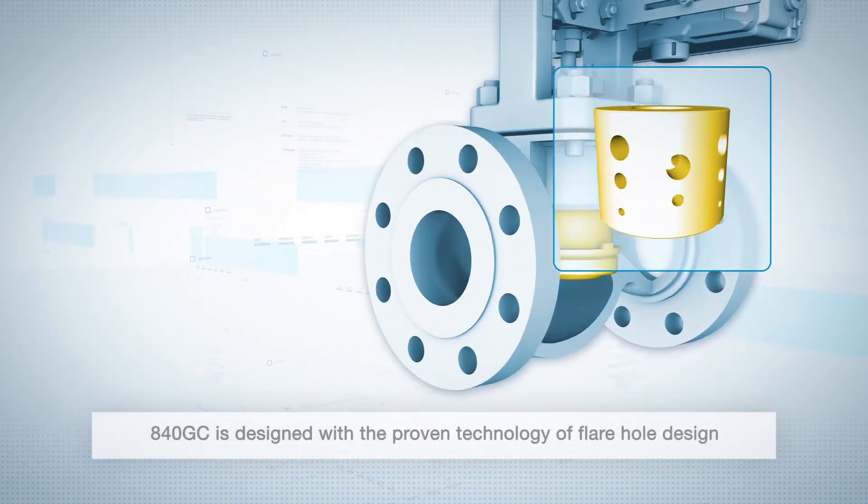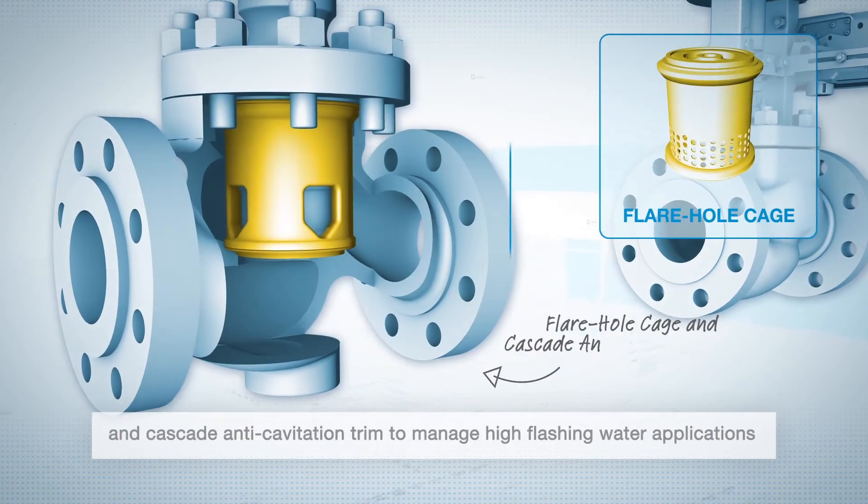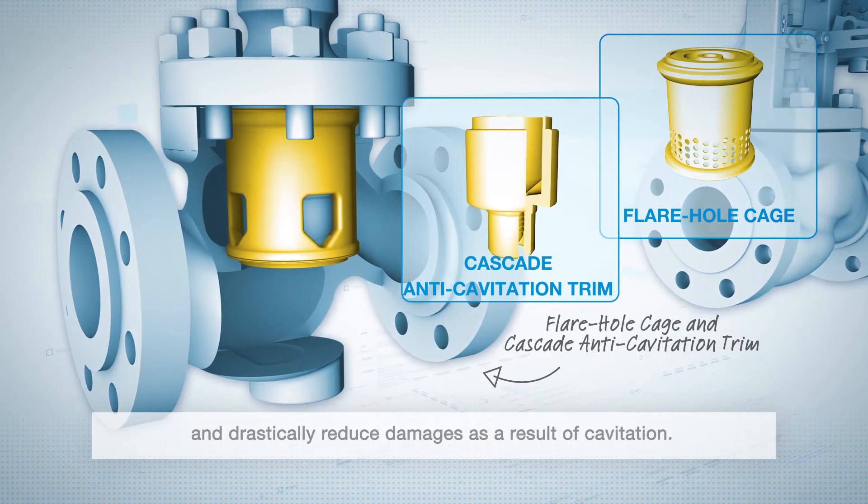840GC is designed with the proven technology of flare-hole design and cascade anti-cavitation trim to manage high flashing water applications and drastically reduce damages as a result of cavitation.